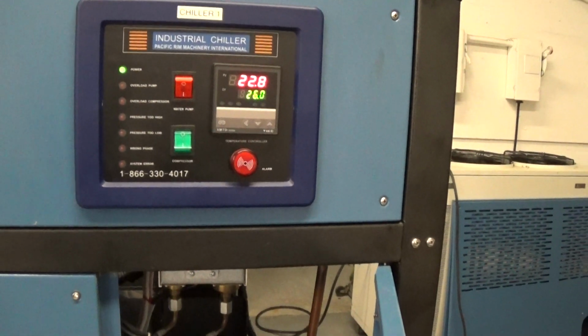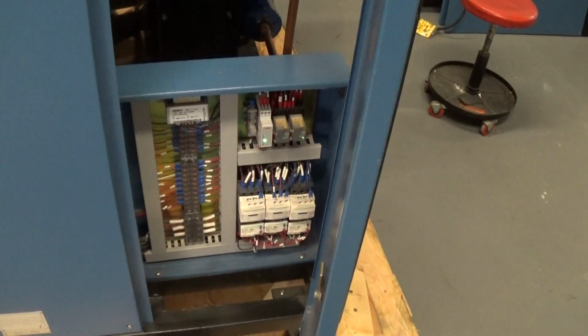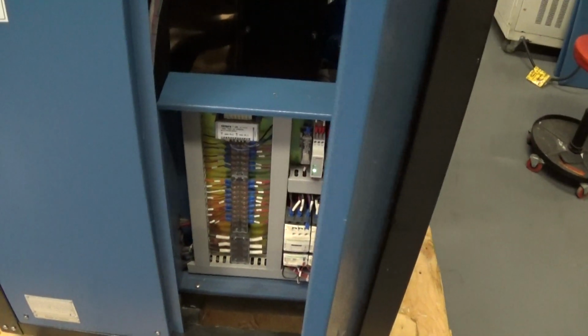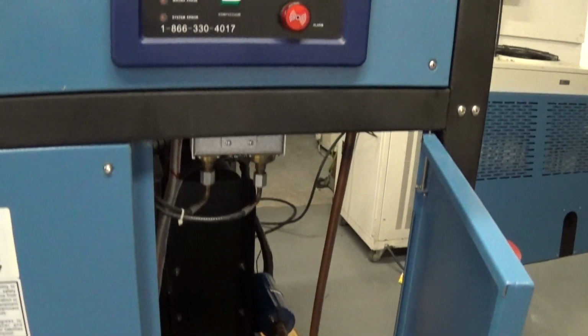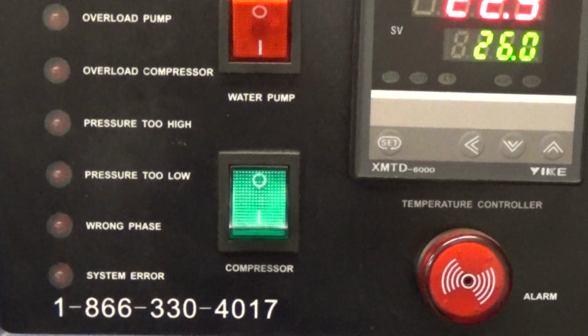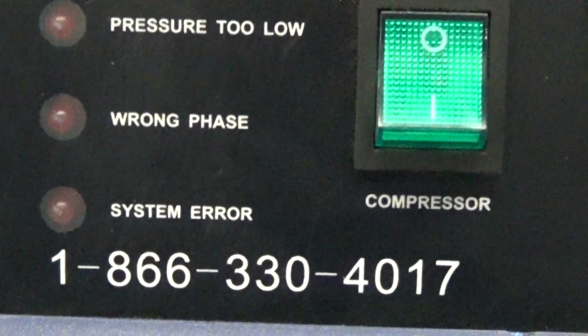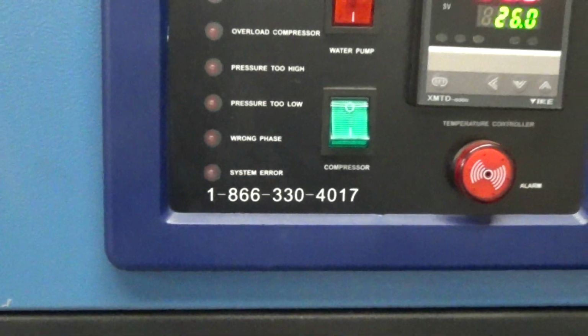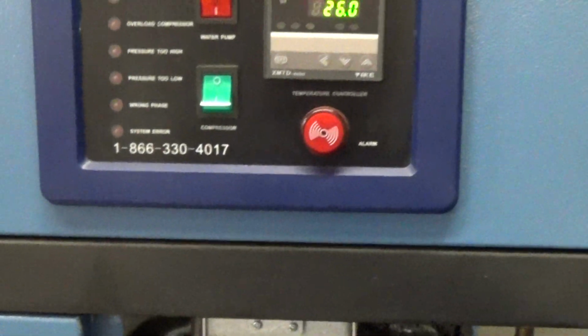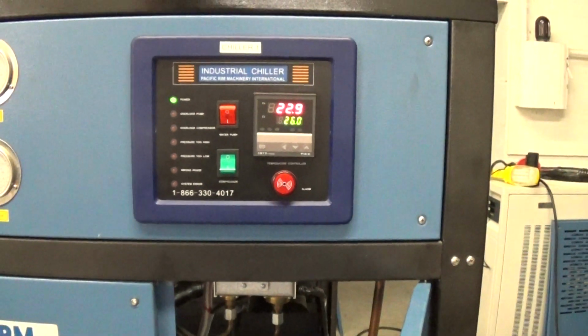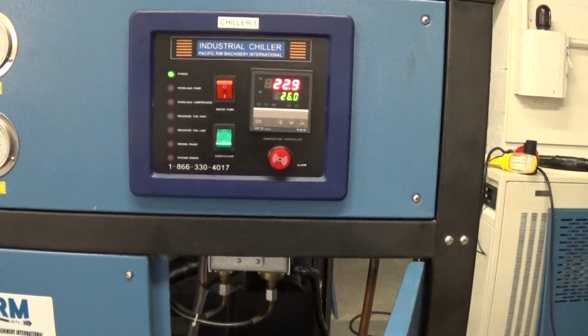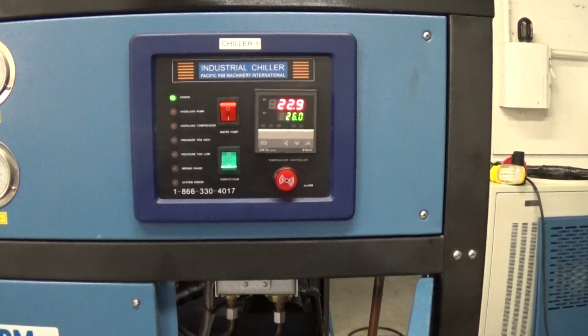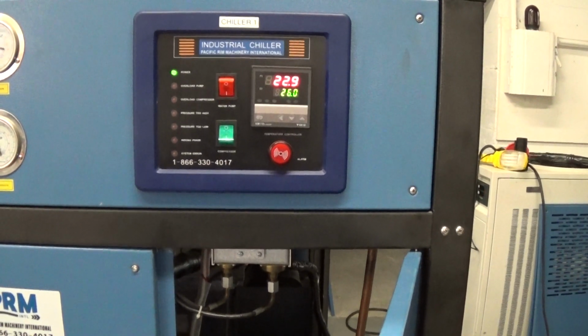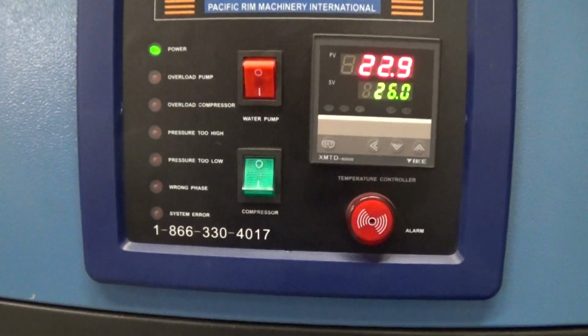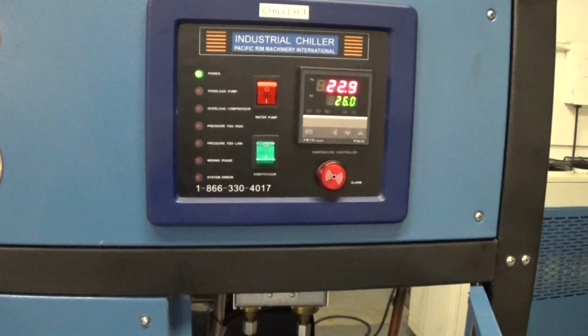When you first put power to the chiller, and that is our electrical area there, if you do have the wrong phase, it is a 460 volt 3-phase unit, you will get the error light that comes on that says wrong phase. If that is the case, you take any 2 of the incoming power leads and swap them. The compressor and the glycol pump are synchronized themselves, so it's the main incoming power that you would swap until you don't have the wrong phase error.